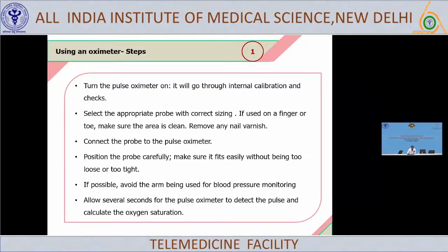If possible, avoid the arm used for blood pressure monitoring, because when you take the blood pressure through the same arm, the perfusion will stop, and artifacts will come up, and it will happen quite frequently. So try to avoid it. Allow several seconds for the pulse oximeter to detect the pulse and calculate the oxygen saturation. Look for the displayed pulse indicator. Each machine will have some signage. It will be like a wave which is coming and going back. Look for this. If it is going appropriately, then probably the readings are acceptable. If there is no pulse signal, then probably it's an artifact. So be cautious of these readings.